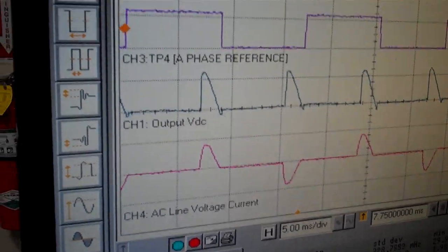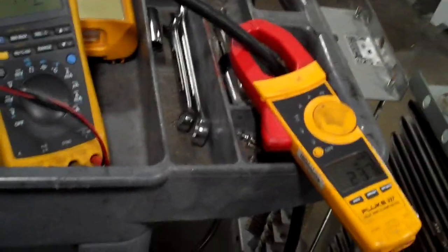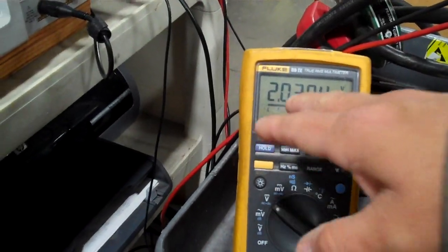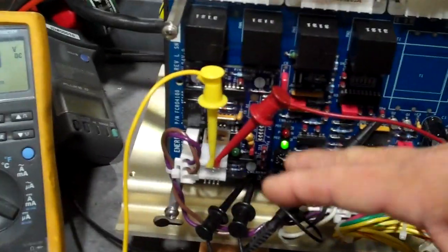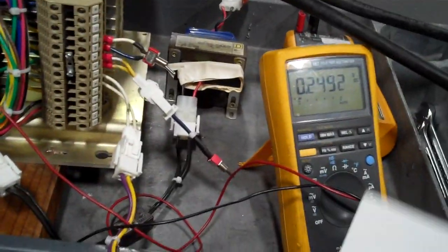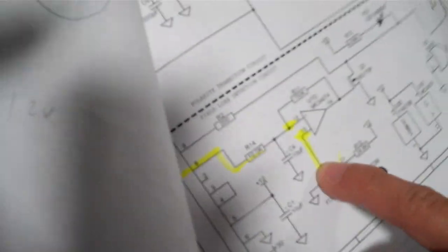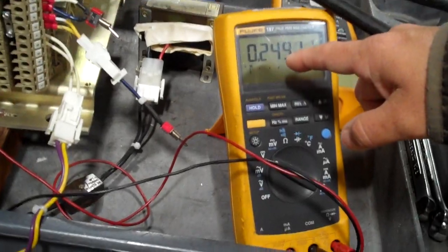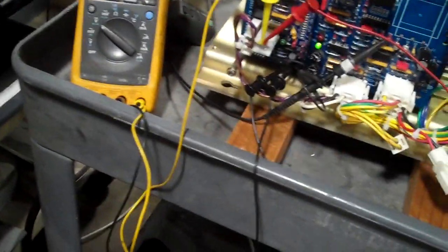So now let's go ahead and start slowly increasing. But what I want to show is our 2 volt threshold on the field loss level never changed, because we had left it at 2 volts on R1 on the PTIFL board. The signal that it's being compared against on the PTIFL is recorded here, and it's approximately 23.7 volts. The feedback is 24 volts, and our threshold is at 2.